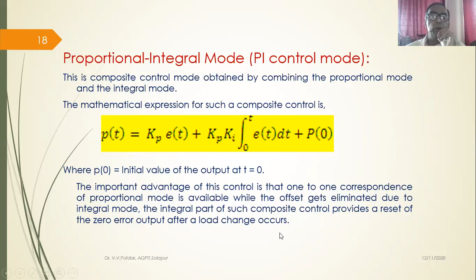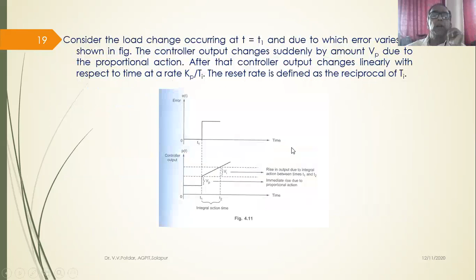The important advantage of this P plus I control mode is that one-to-one correspondence of proportional mode is available. So both the benefits of proportional control action and integral control action are combined. The offset error, which was a problem with the proportional controller alone, is also eliminated due to the integral mode. So the integral part of such a composite control provides a reset of zero error output after a load change occurs. This is the explanation for offset error elimination.